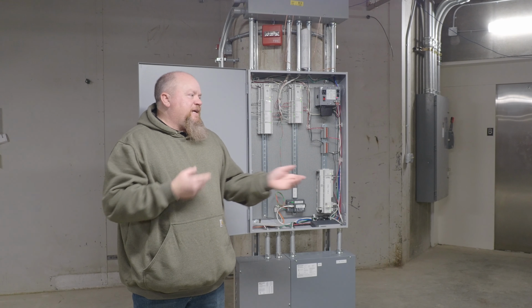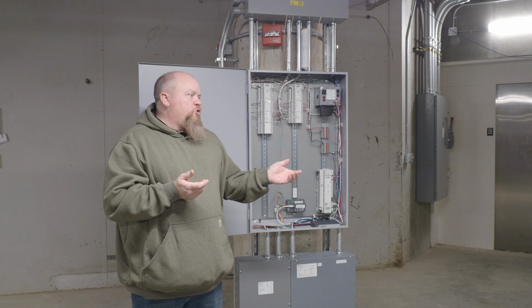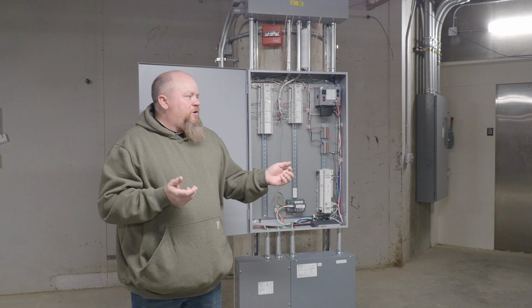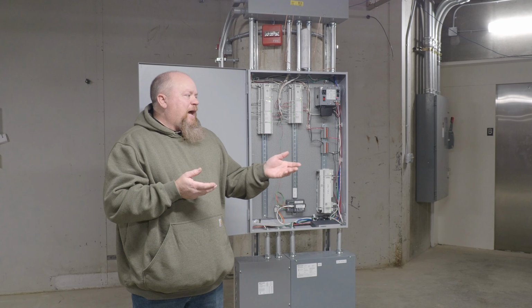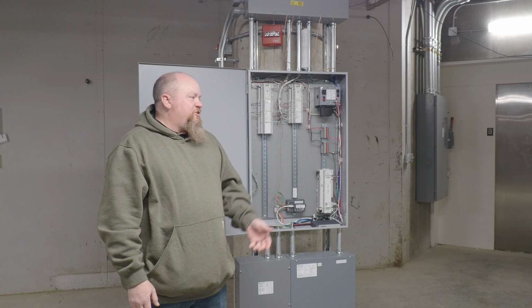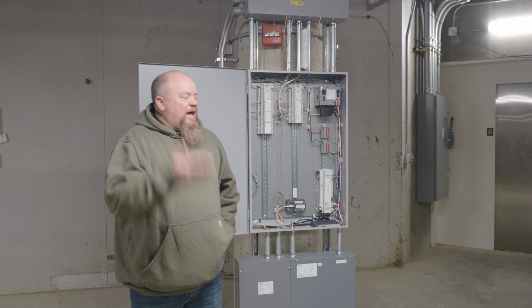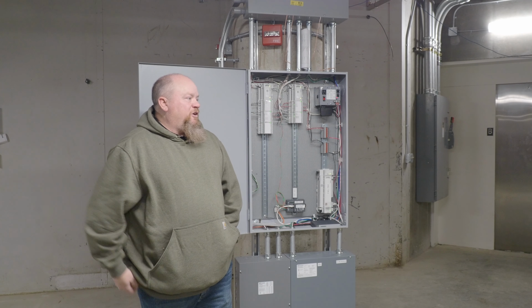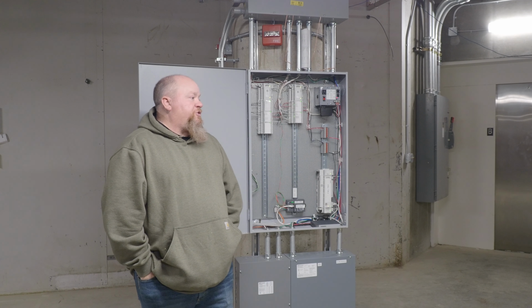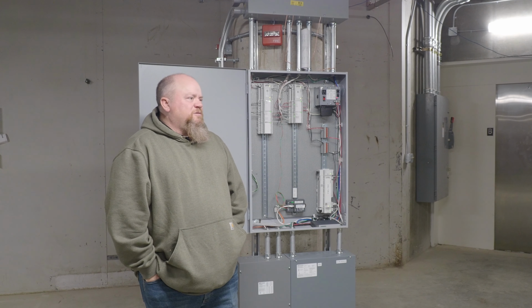I think it's 150 GPM per boiler. So anytime there's more than 2 valves open, I ramp those pumps to 100%, because anything else, I'm trying to control water flow that I can't achieve. It wants GPM, I can only get 400. I think it's 400, somewhere around there.